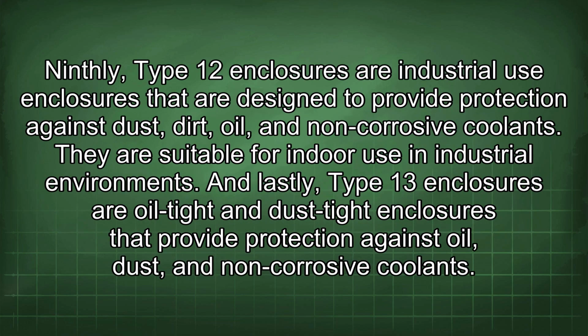Ninthly, Type 12 enclosures are industrial use enclosures that are designed to provide protection against dust, dirt, oil, and non-corrosive coolants. They are suitable for indoor use in industrial environments.